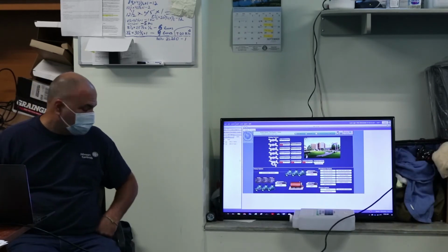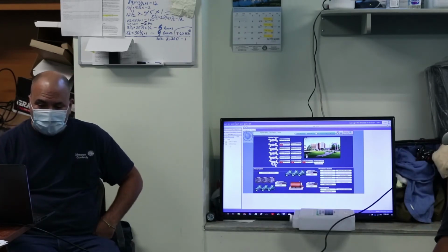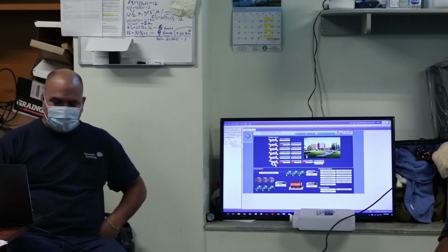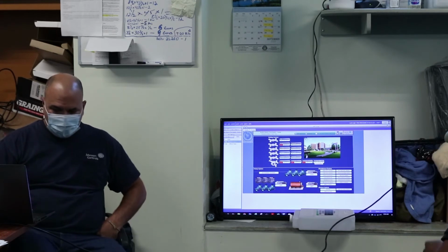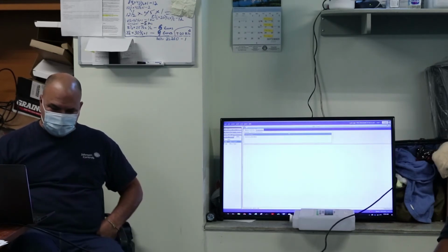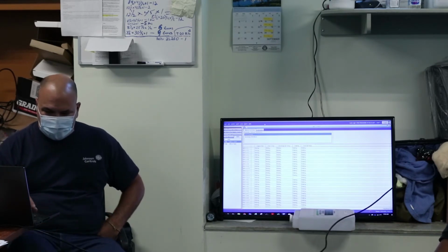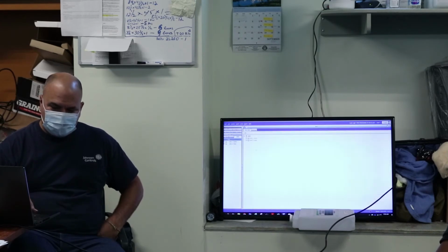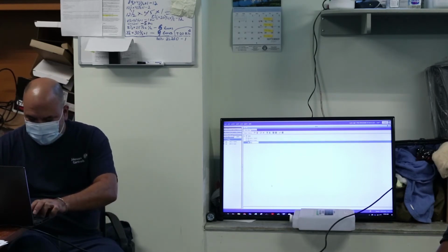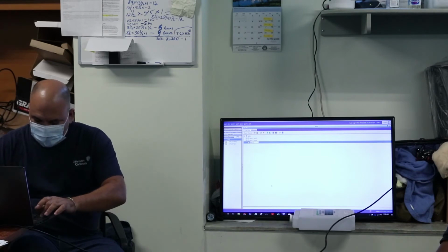So in the user view, right? See the tabs, right? So I created one for the new building, and what I did was I added VAVs for AHU 1 and 2. This is what you're talking about, right? Yep. So let's create another one. We'll do AHU 3 now. I'm going to drag or double click this tab and bring over the whole point. I hit edit. So I'm going to add a folder, and I will call this one AHU 3 VAVs.